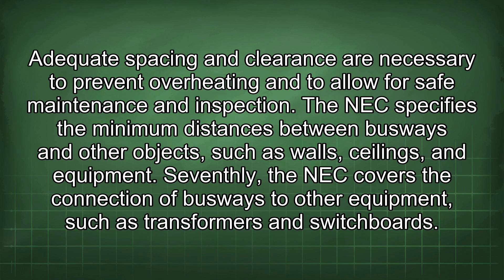Seventhly, the NEC covers the connection of busways to other equipment, such as transformers and switchboards. These connections must be made in a way that ensures a reliable electrical connection and prevents mechanical stress on the busway. The NEC specifies the types of connectors that can be used and the torque requirements for tightening the connections.